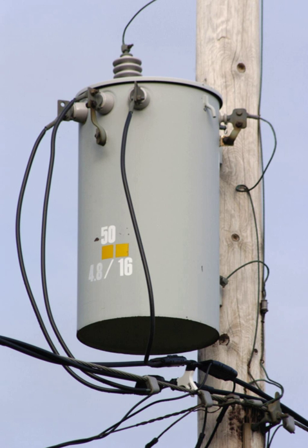Closer to the customer, a distribution transformer steps the primary distribution power down to a low-voltage secondary circuit, usually 120/240 volts in the U.S. for residential customers. The power comes to the customer via a service drop and an electricity meter. The final circuit in an urban system may be less than 50 feet (15 meters), but may be over 300 feet (91 meters) for a rural customer.